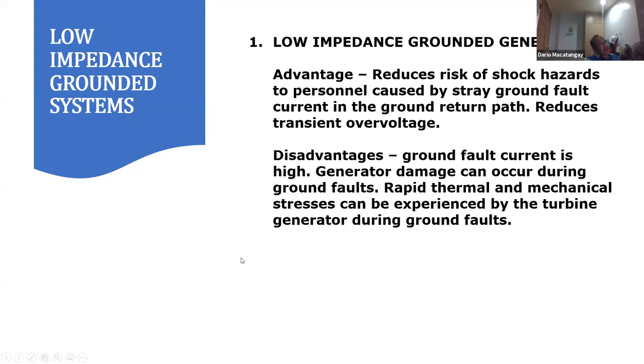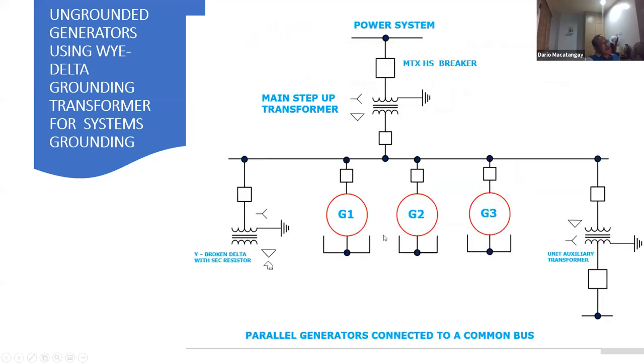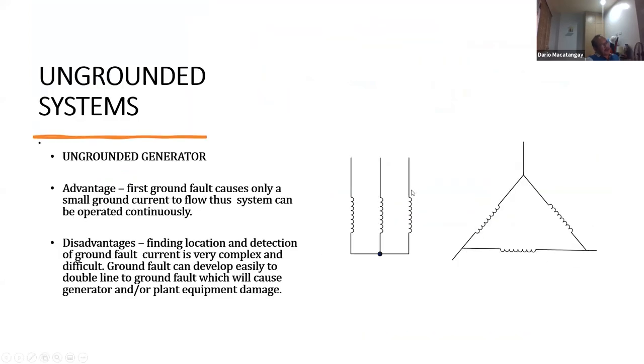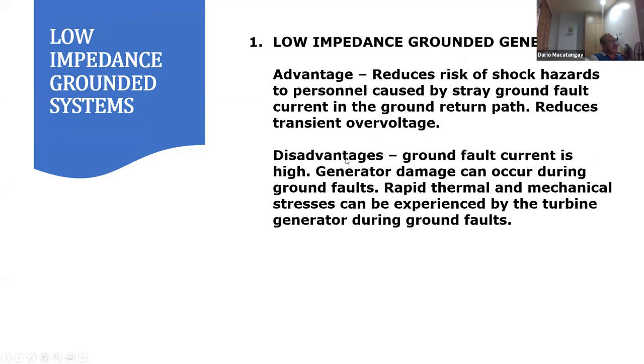By the way, this transient overvoltage, going back to the ungrounded system, when you have a ground fault here, the voltage on the healthy phases will increase. The line to ground voltage can approach the line to line voltage value, even higher. So we're exposing this winding to higher voltage. But if you're using a low impedance grounded generator, and you are just using a small value of resistance on the neutral, you're actually reducing the transient overvoltage.